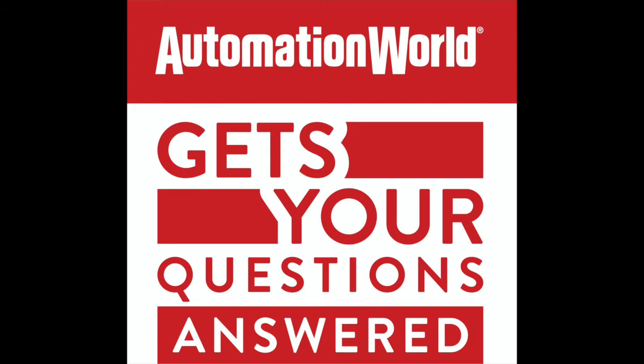Okay. And where and how is this typically applied? And by that I mean on what types of equipment is it typically used and what does it tell a manufacturer? Sure. So mean time to repair is usually a reflection of maybe your maintenance team's performance, as well as the nuisance level of a piece of equipment or the implications of its downtime. So, for example, if most of your MTTR on most of your assets is something like 10 to 20 minutes, but one key piece of equipment has an MTTR that's measured in hours or maybe even days, it really can help you prioritize to figure out what's the most important thing to keep running.